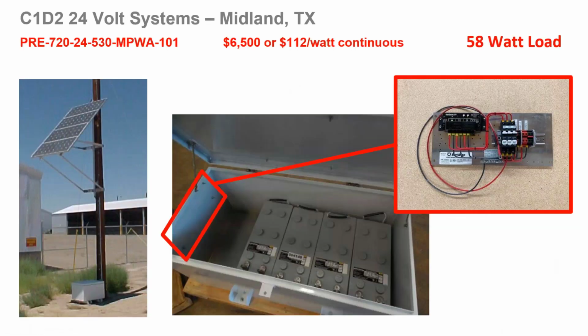So visually, what do these 24 volt systems look like? Well, we have a side of pole mount array with 4 of our 180 watt modules, and a chest style enclosure on the bottom with 4 of our Group 8D batteries wired 2 in series, 2 in parallel for 24 volts. You can see our Sunsaver control panel mounts on the left-hand side of the enclosure.